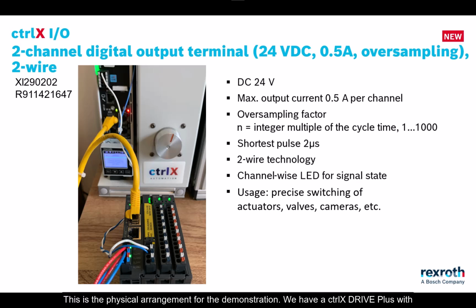This is the physical arrangement for the demonstration. We have a ctrlX Drive Plus with integrated ctrlX core. This is the EtherCAT master interface. It is connected internally to the host drive and to this ctrlX EtherCAT I/O coupler. Connected to the coupler is the Oversampling Digital Output Module we are testing, along with a standard digital output module and a standard digital input module.